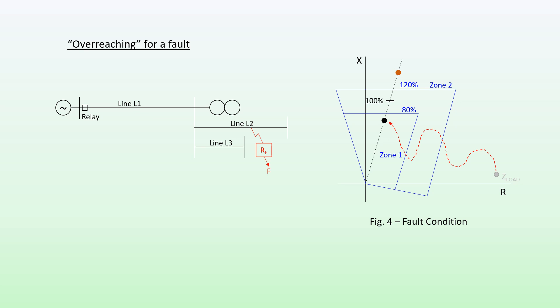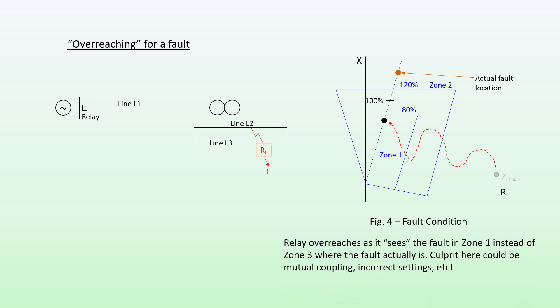The actual fault lies in the Zone 3 region — that is where the actual fault location is. So we can see that the relay overreaches, as it sees the fault in Zone 1 instead of Zone 3 where the fault actually is. The culprit here could be mutual coupling, incorrect settings, and so on.